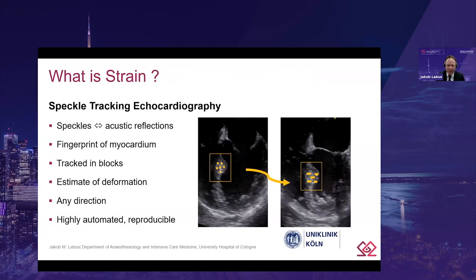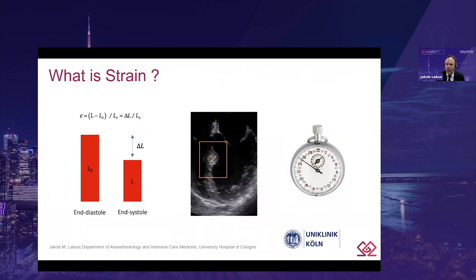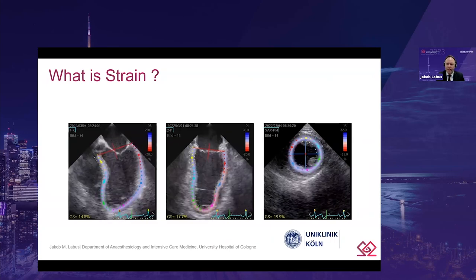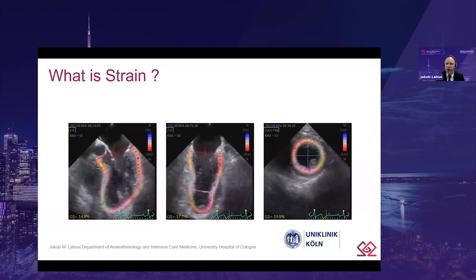What is speckle tracking? Speckles are bright and dark pixels in a 2D B-mode view — they are acoustic reflections whose spatial relationships form a fingerprint of the myocardium. Speckles can be tracked in blocks through the complete cardiac cycle, giving an estimate of myocardial deformation in any direction. This process is highly automated and highly reproducible. So myocardial strain is a change of myocardial length over time, measuring the movement of typical acoustic reflections — the so-called speckles — tracked during the entire cardiac cycle.